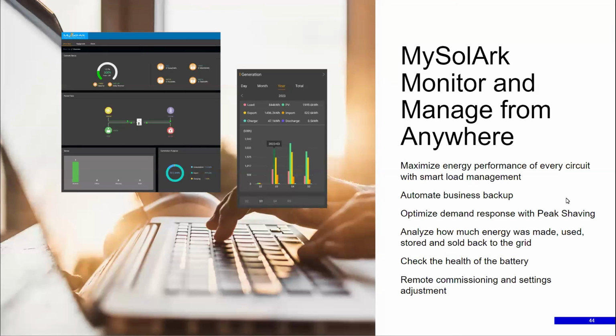It depends. If you're looking at putting in a manual throw switch, then you may have to figure out overcurrent protection in that line. I think what is more pragmatic, sometimes this is called a Hawaiian tie-in, but it's not really the traditional definition of a Hawaiian tie-in. But basically, on the grid side, my favorite budget way to get over this aspect is to put in a double lug off the grid side and pull a circuit onto a generator interlock switch at the top of your service panel. And that will give you 40 amps or 60 amps, whatever the size of the manual throw switch of the generator interlock is, for servicing. And that will give you power while the system is offline.